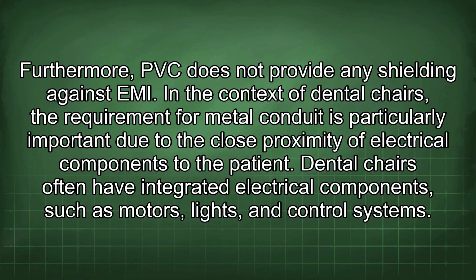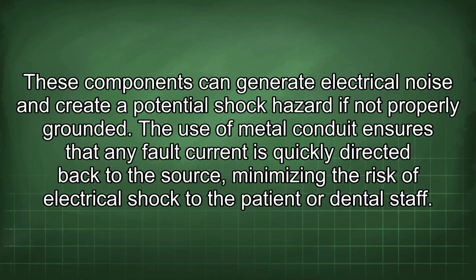Dental chairs often have integrated electrical components such as motors, lights, and control systems. These components can generate electrical noise and create a potential shock hazard if not properly grounded. The use of metal conduit ensures that any fault current is quickly directed back to the source, minimizing the risk of electrical shock to the patient or dental staff.